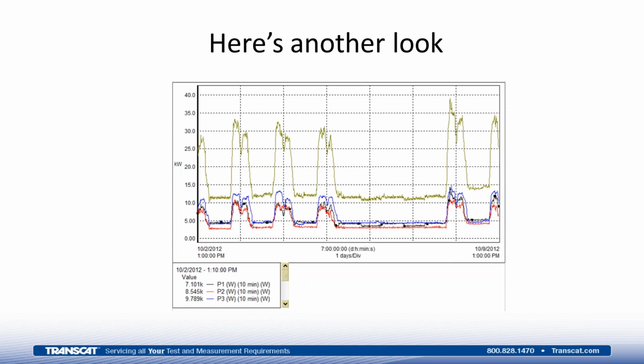In this case, I could see peaks over 25 kilowatts up to 32, and in one case it went all the way up to 37 or 38 kilowatts being drawn on this particular load. By graphing it in this way or accumulating the data and then presenting the graph, it gives me the ability to look into the energy usage and make decisions on how I might be able to reduce or regulate the energy usage within a facility.